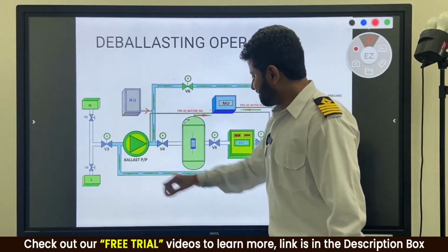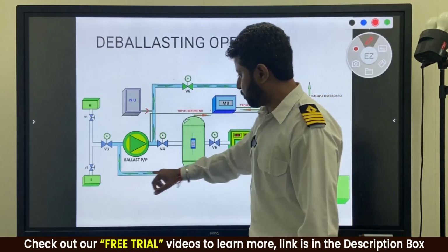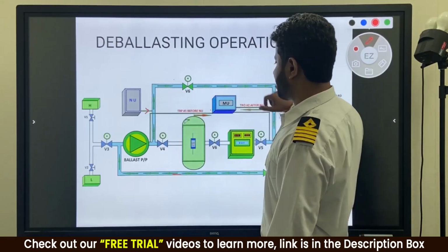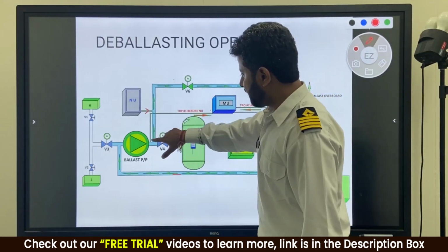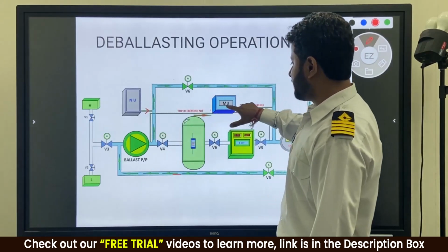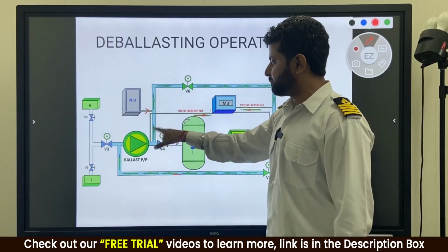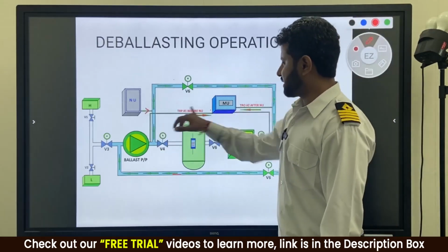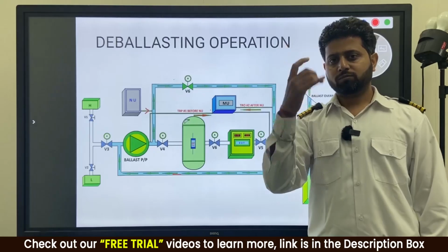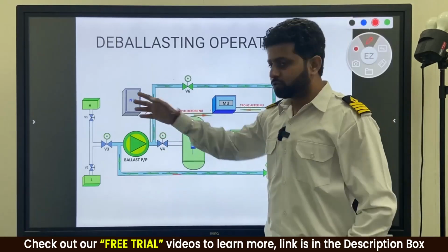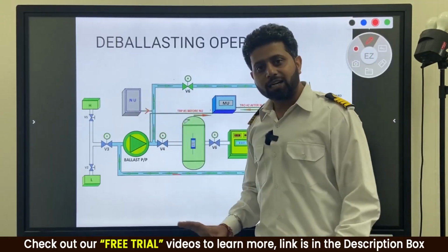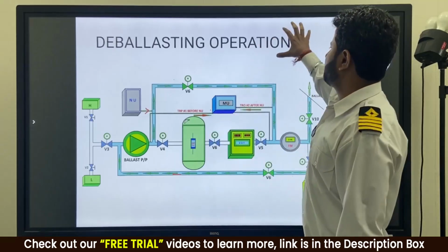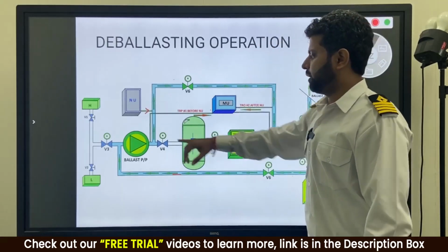Now when this ballast water tank water is coming over here and trying to go overboard, one solenoid valve opens and tells us how much active oxidant is present over here. If it says from this sample the active oxidant is 0, that means this neutralizer unit is not needed, so it does not start. The main panel says there are no problems, it is 0.